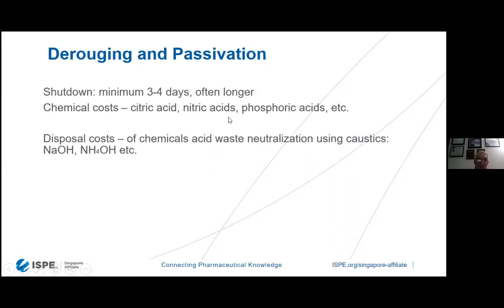It costs money. But in order to get rid of those chemicals that are in the water, we have to do what is called acid waste neutralization. That's using caustics against the acid in order to bring the pH to as close to 7 as possible. In Singapore, as an example, where water is recycled through NEWater, bringing up the pH is extremely important because there are only certain levels of pH that are able to be dealt with in NEWater. And the water that goes back for recycling needs to have a pH close to 7. So using sodium hydroxide or ammonium hydroxide is how that happens.